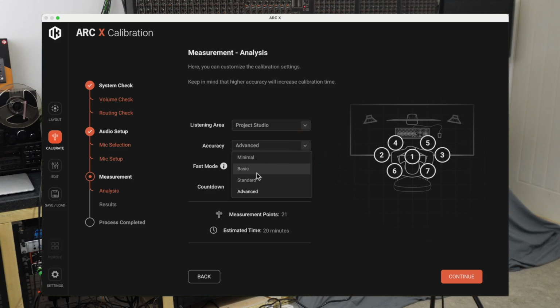Okay, so we're going to go with standard. Now finally, there's a countdown. That's how long you get from when you activate each calibration point recording to get out of the way of the speakers and the mic before the calibration recording process takes place for that position. I'm going to leave it in the default 5 seconds. And we're ready to go.